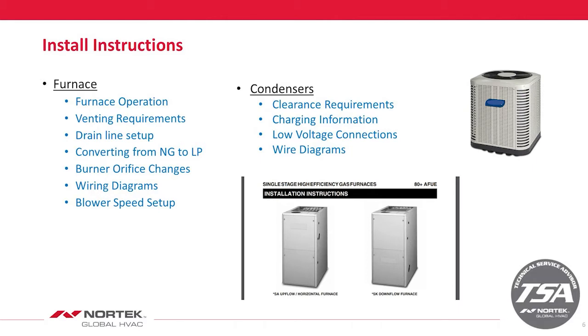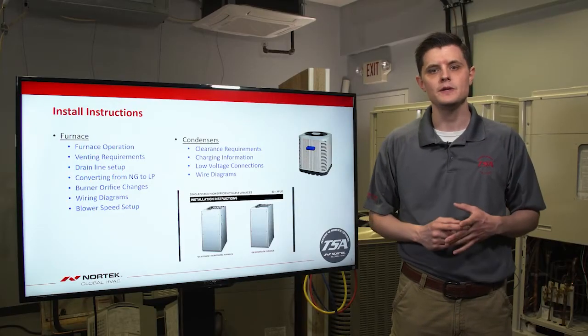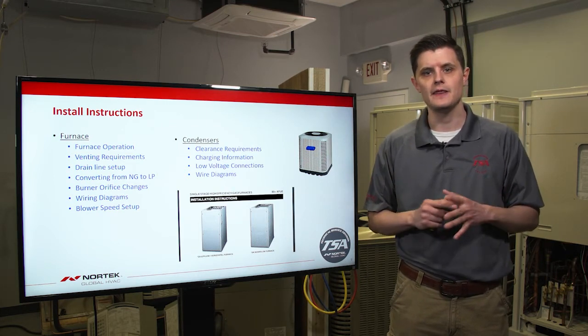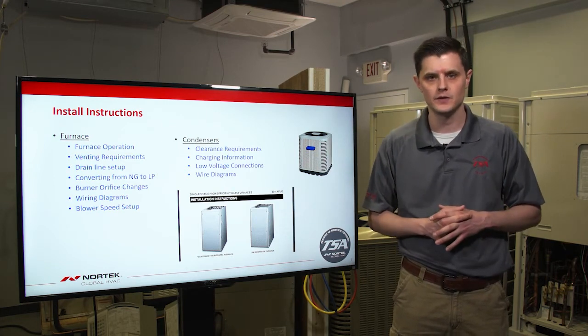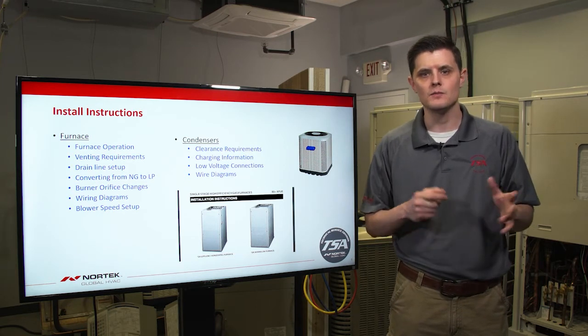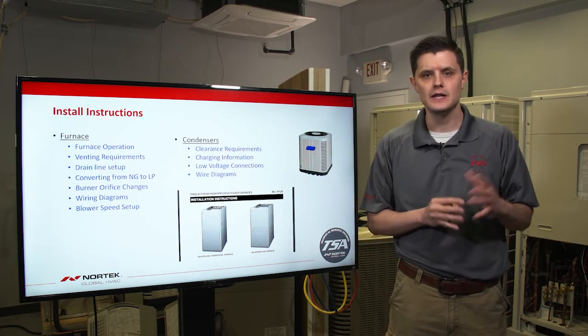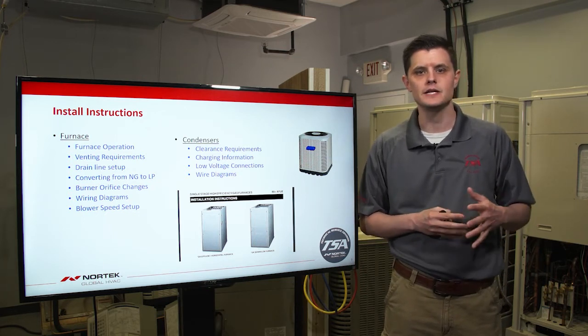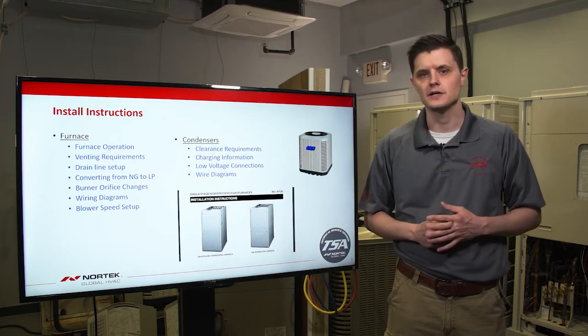We also put wiring diagrams in the install instructions along with the blower speed setup. If you're looking at older install instructions, that blower speed setup will be in there. If you're installing brand new equipment, we actually put a separate blower chart in the packet for that particular furnace—so on new equipment it's separate from the install instructions, while on older equipment it's included within them.